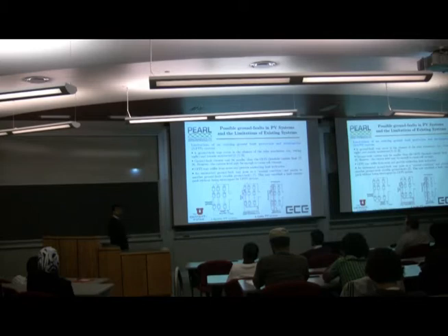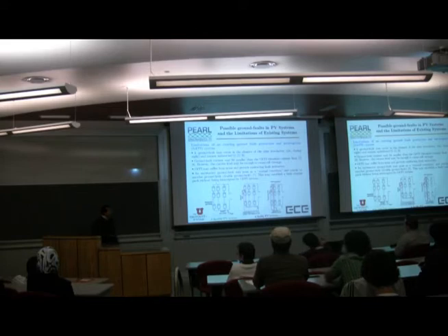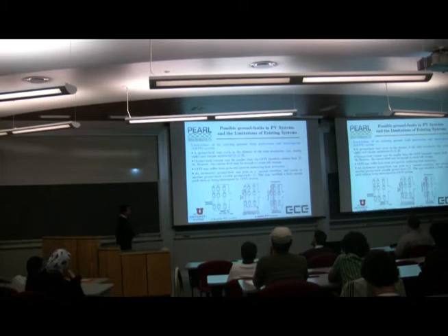And what we do to prevent this fault is we have a fuse and we have a protection circuit which we call the GFPI, the ground fault protection and interruption circuit. In most cases they work, but in some cases they will not work. Because if the short circuit current is less than the sensitivity of the GFPI, it would not trip the GFPI. And in many cases, the fault may occur at night. There is no illumination or radiation, which means the fault current is not high enough to blow the fuse or activate the GFPI, and you still have the short circuit current.